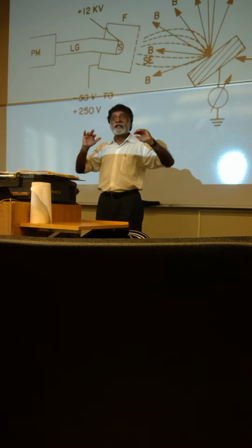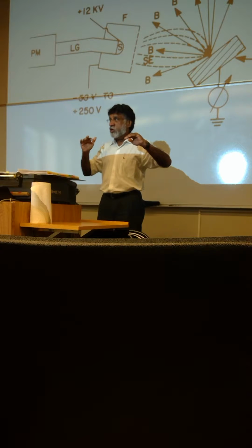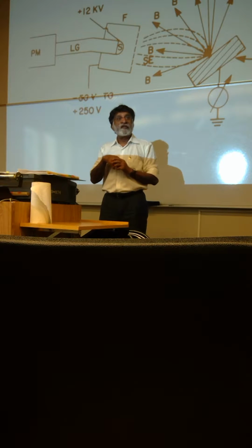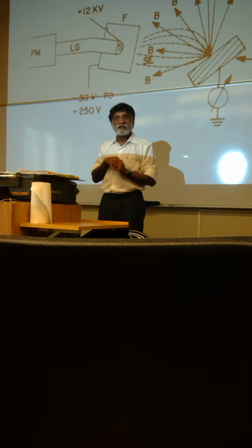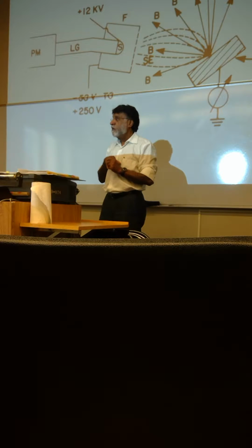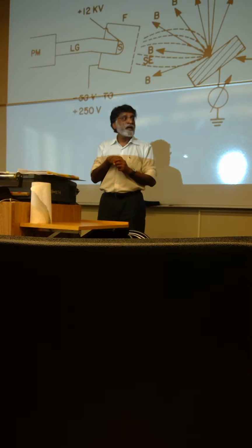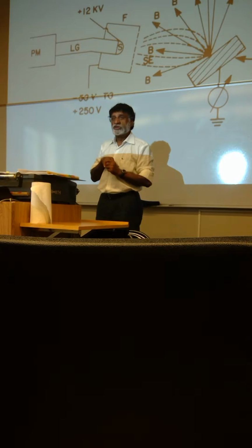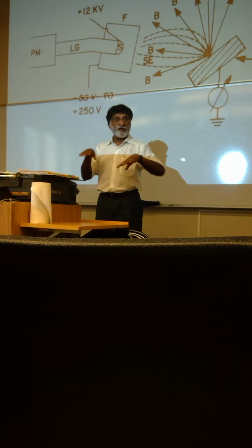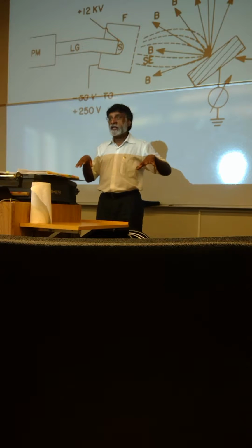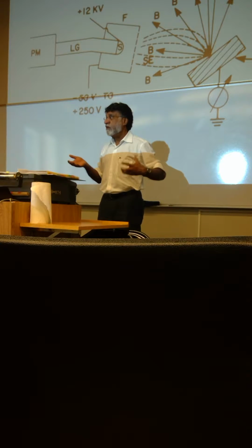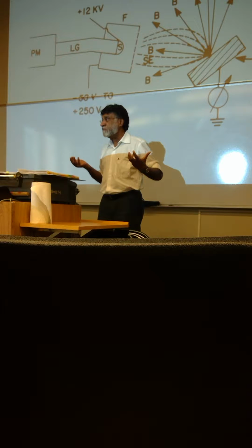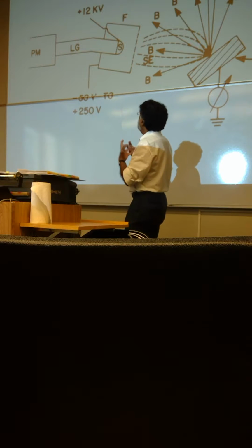But when you look at the backscattered electrons, you get contrast from the topography, plus contrast from the chemistry of the sample, the composition, the average atomic number. So if you have different elements in different parts of the sample, you will get sensitivity to that in the backscatter. Okay? So you need to detect these electrons.